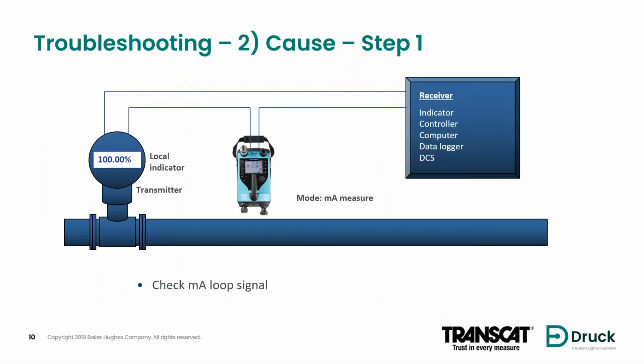So here we are at our location, and this is a simplified schematic to illustrate that here's our troublesome pressure transmitter connected to a quote-unquote receiver, which could be just a simple indicator, controller, computer, data logger, DCS system, PLC, you name it. So probably the first thing that we want to do in our troubleshooting effort is to do a loop check, make sure we actually have continuity from the transmitter to our controls. If we don't have that, then there's something probably wrong with the cabling, although I'm going to hold off drawing conclusions till the end.